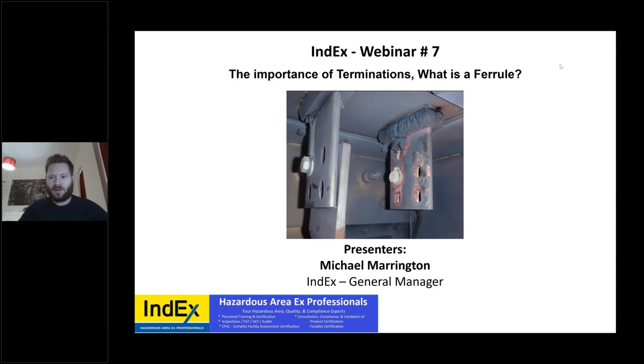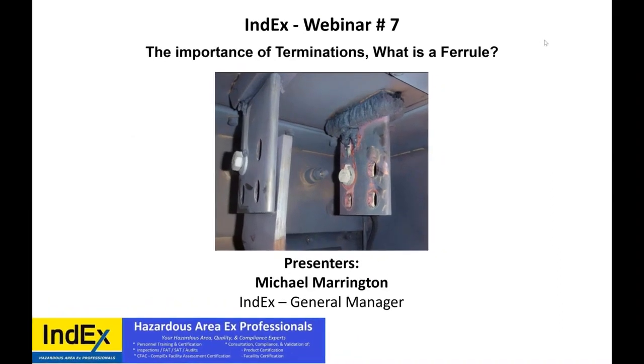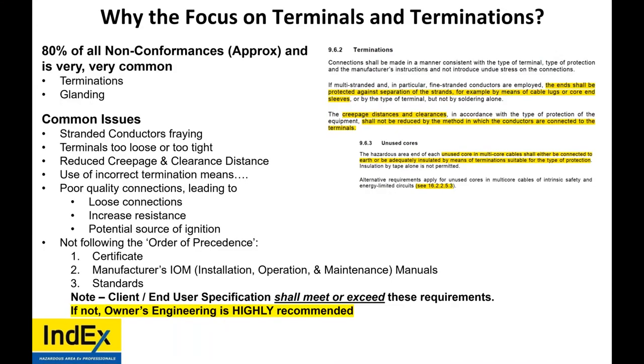I'm going to turn off my camera now so that you guys can concentrate on the presentation. Okay, so why the focus on terminals and terminations? Well, it's mentioned in the standards quite a few times that ends shall be protected against separation of cable strands, for example by means of cable lugs or core end sleeves. Creepage and clearance distances are mentioned. Unused cores are mentioned.